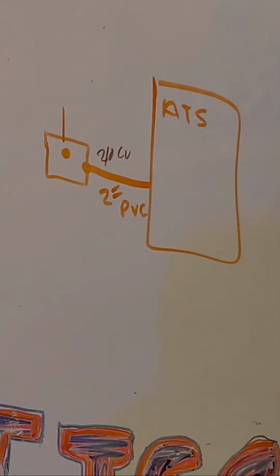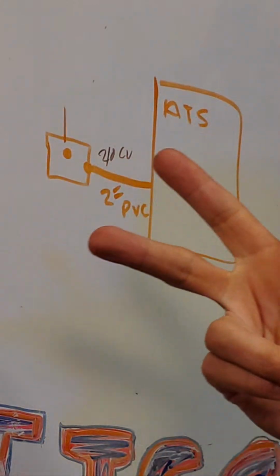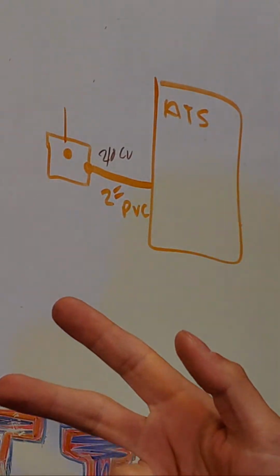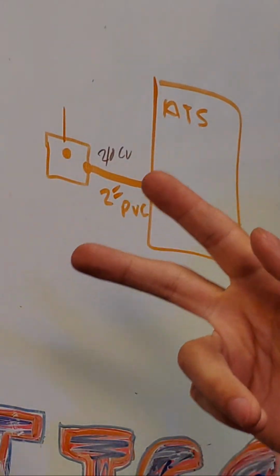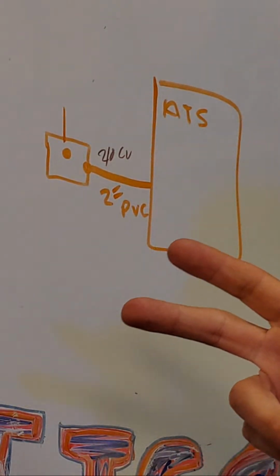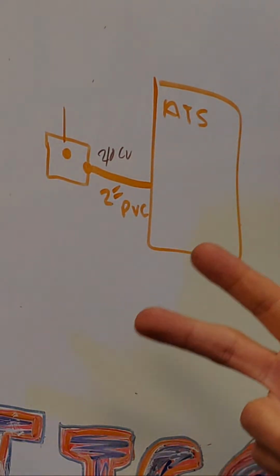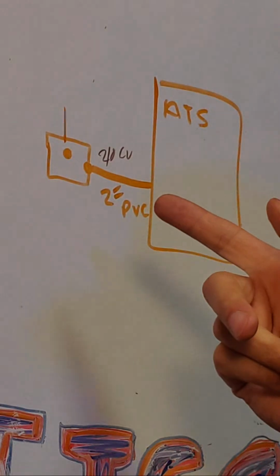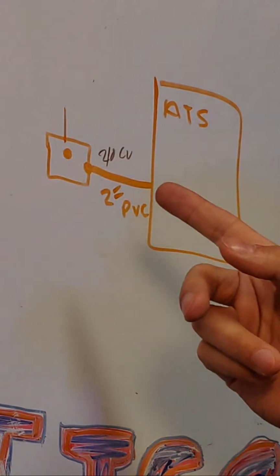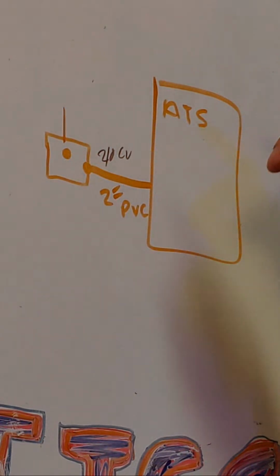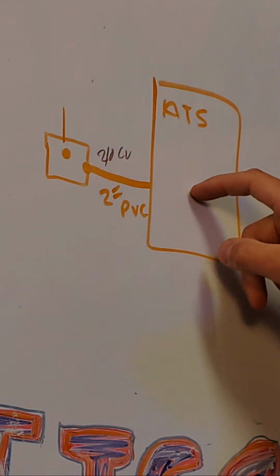Actually had good service grounds—he had 3 grounds in there. Two grounds that were service and one ground that was equipment, and they were isolated properly. He did irreversible crimps in the original panel because grounding electrodes have to be continuous—they've got to be irreversibly crimped or CAD welded or something like that. So he irreversibly crimped the cold water and the ground rods, sent them back through this box, and then had a separate equipment grounding conductor on the isolated sub panel that went out to the source, which was the ATS. Did a really good job on it.